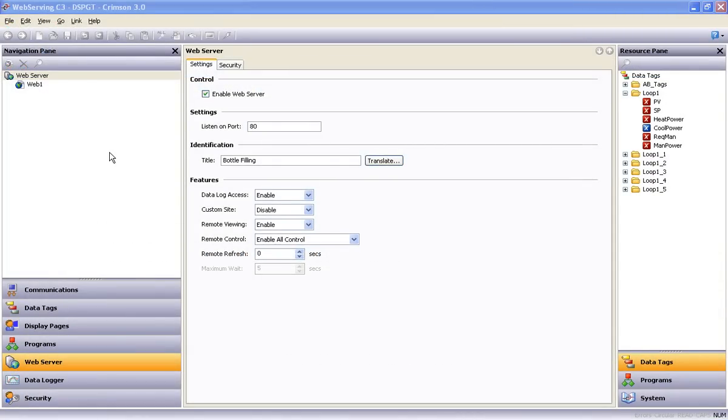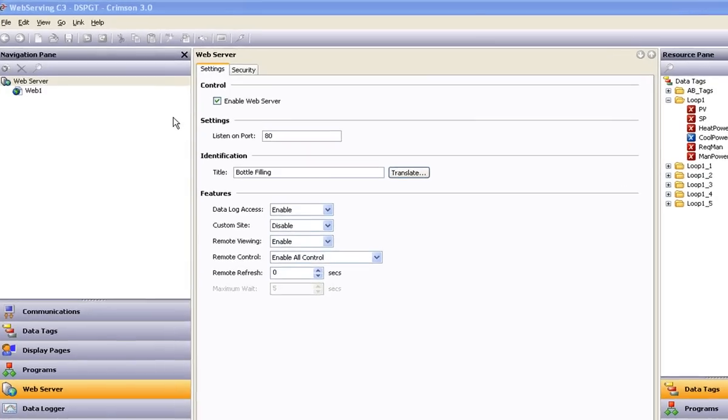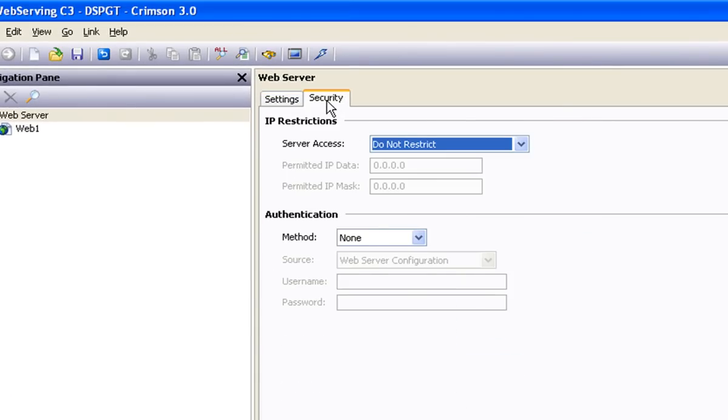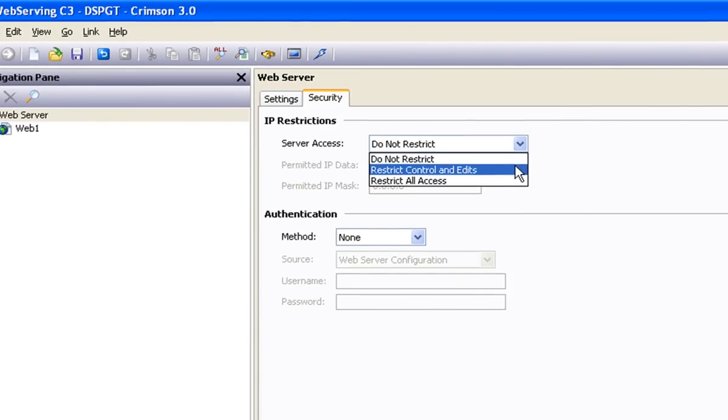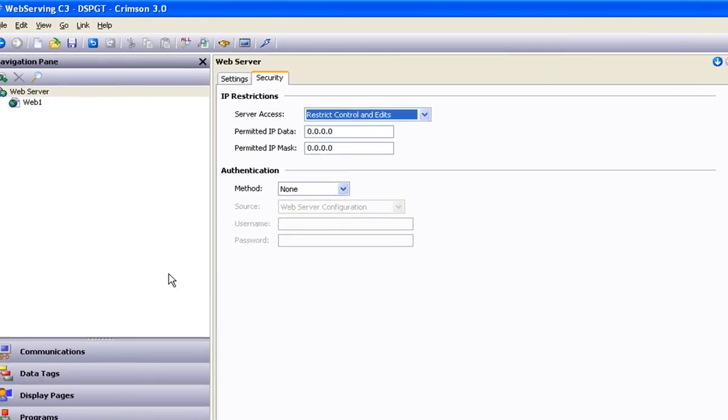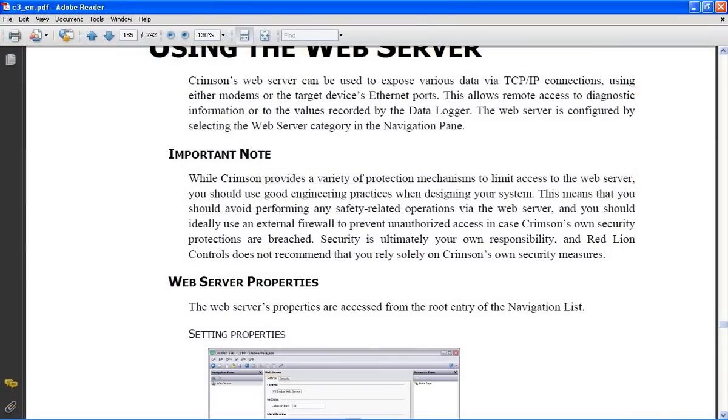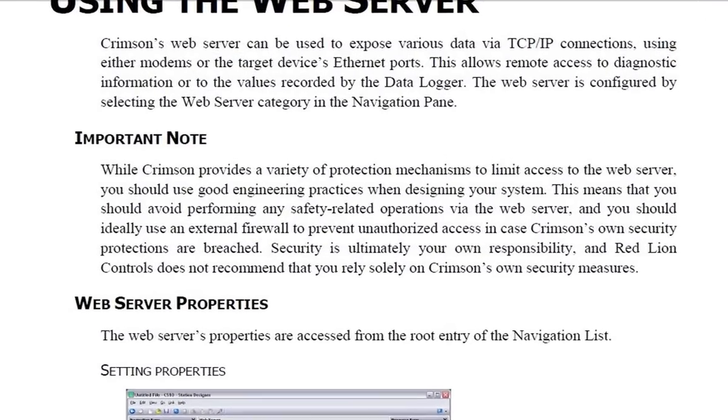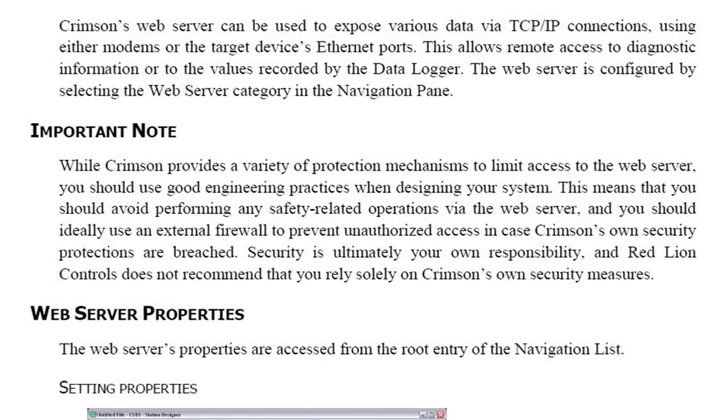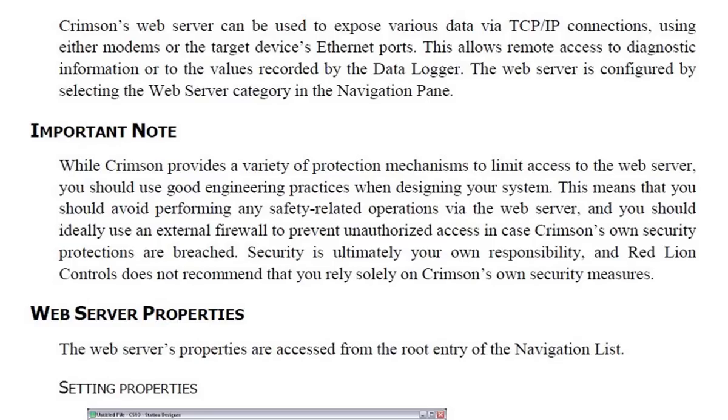And lastly, one thing we didn't talk about throughout this video was the issue of securing access to your application from every other human being on the planet with a PC and an internet connection. Although there are several layers of security that can be invoked within Crimson 3, I will read an important note from Crimson 3's help file concerning this matter. While Crimson provides a variety of protection mechanisms to limit access to the web server, you should use good engineering practices when designing your system. This means that you should avoid performing any safety-related operations via the web server, and you should ideally use an external firewall to prevent unauthorized access in case Crimson's own security protections are breached. Security is ultimately your own responsibility, and Red Lion Controls does not recommend that you rely solely on Crimson's own security measures.